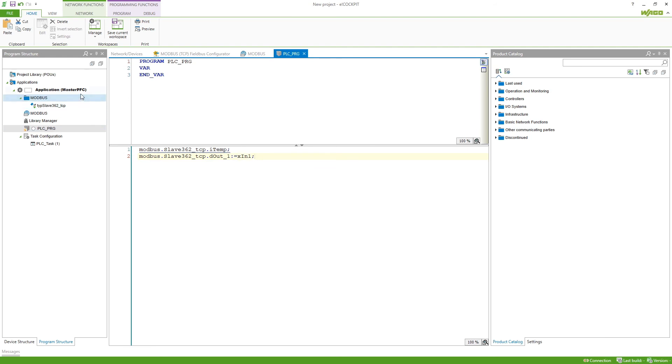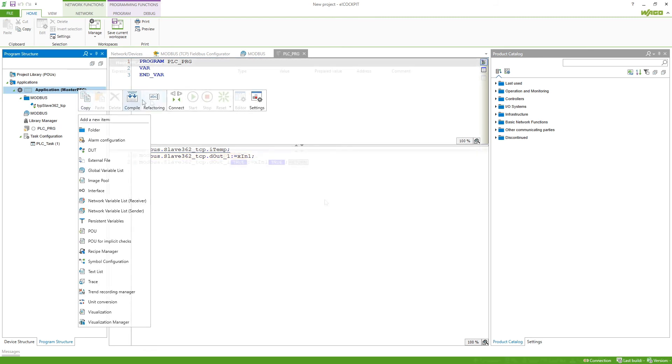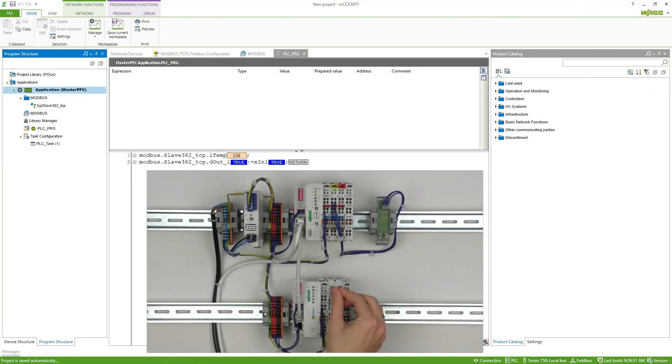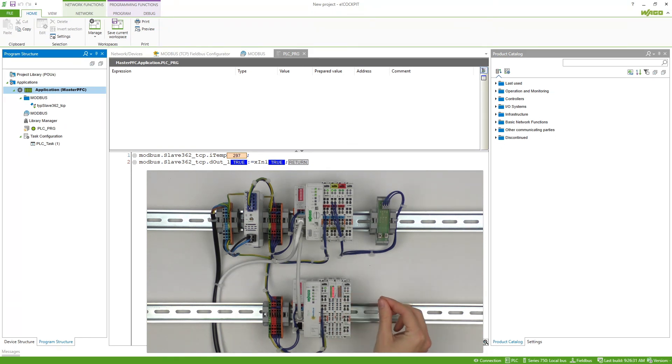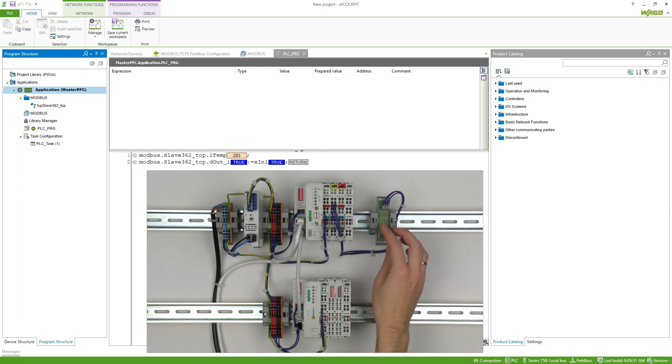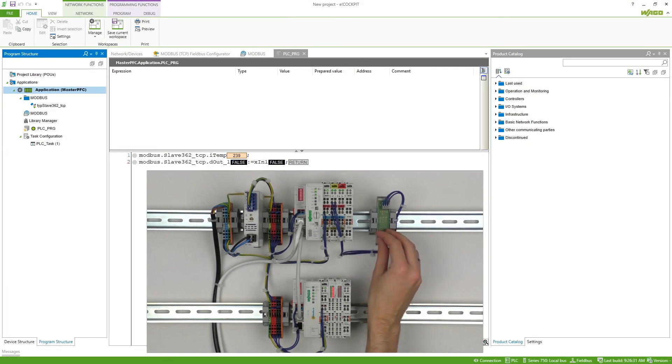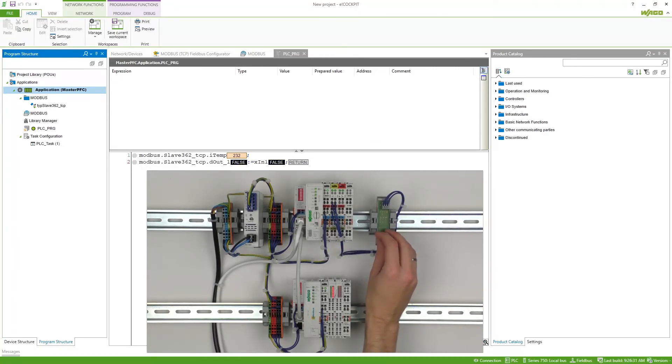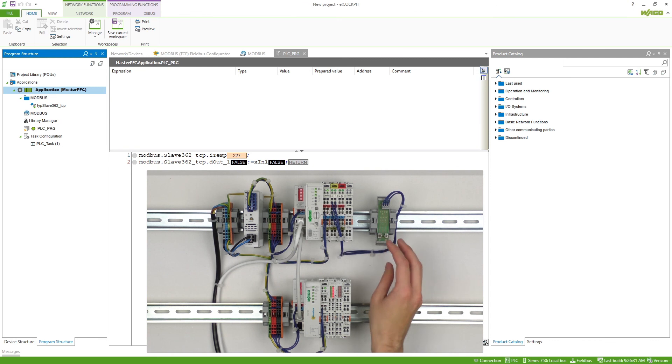Now if we connect we can already test our configuration. So now we can see that we've got a temperature of 23.4 degrees here and if I touch this thermal element we can see that this will rise up. We can already see since the digital input is already active that our digital output is active and if I now use this button here we can see that it also triggers the digital output of our Modbus coupler.